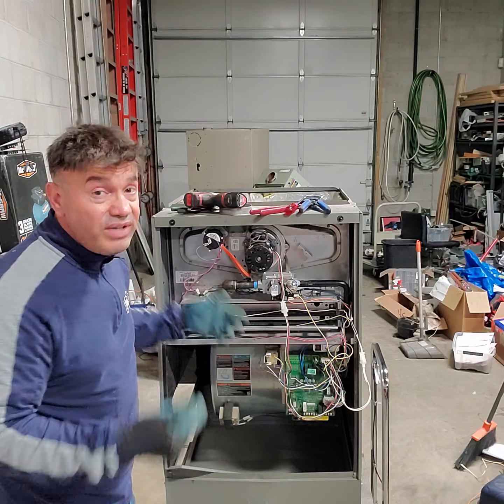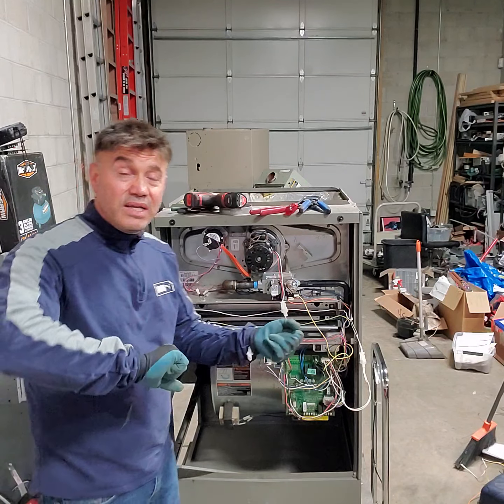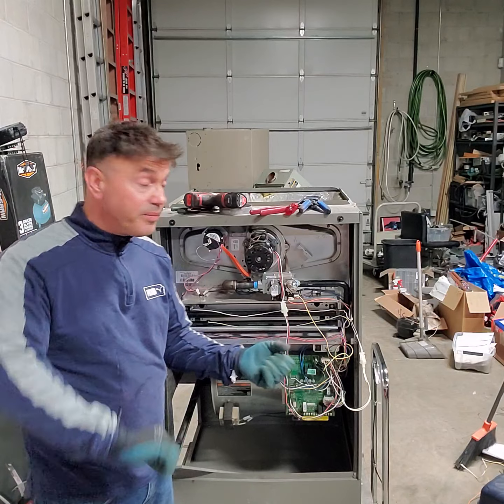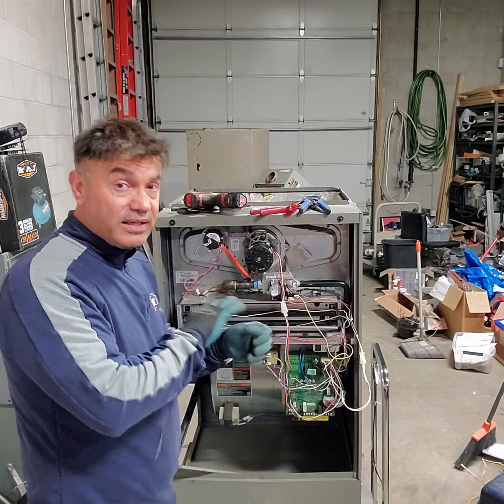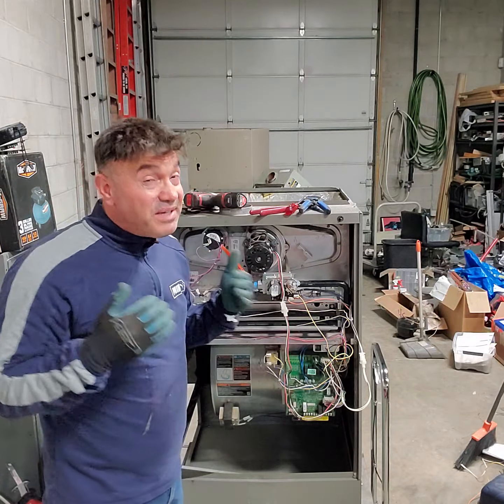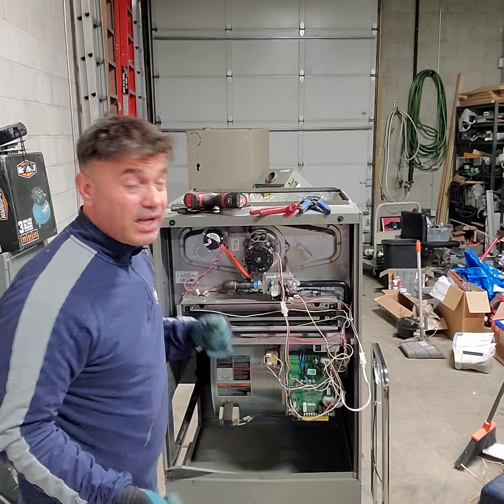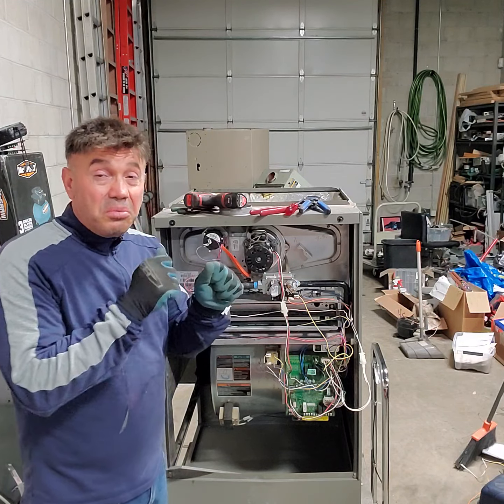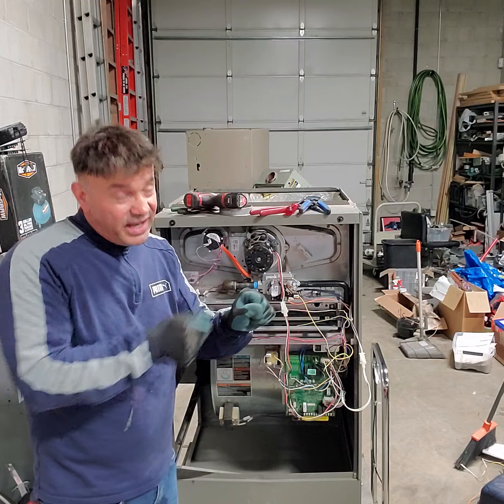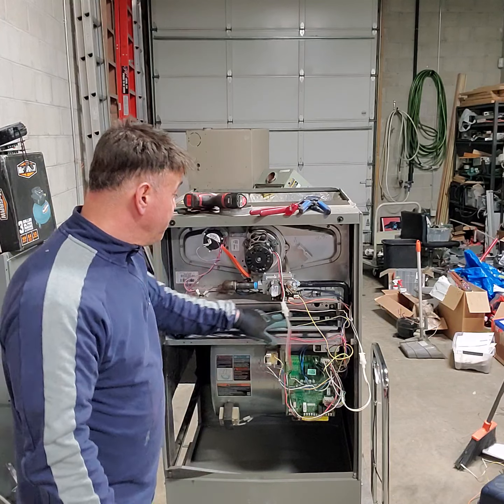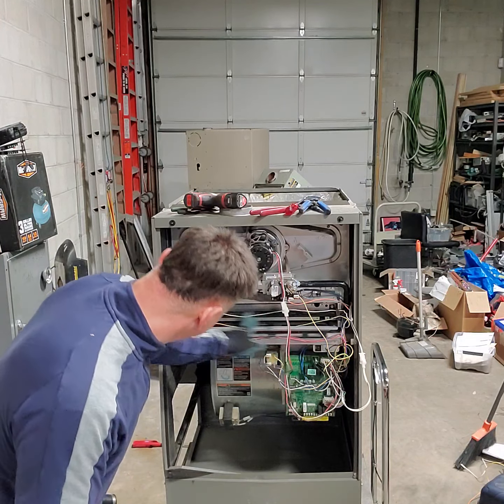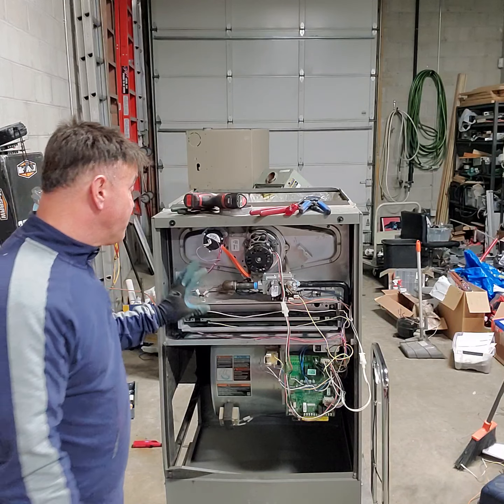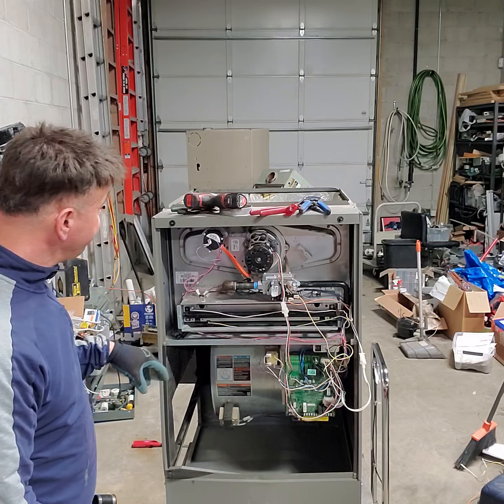All you have to do sometimes, if you have a CO2 tank - but don't go crazy - you can just blast it and clean it. In some cases I have to take the whole assembly out and literally clean every injector with a wire brush, because it was only firing a couple of them. The last one here was not firing. So these are the things you need to know about the flame sensor.